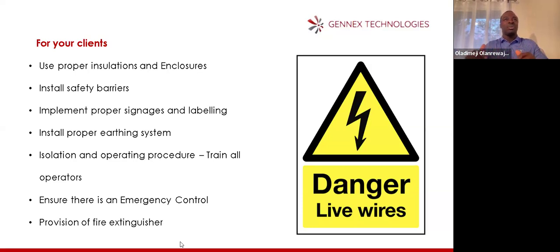I've gone to a site where all the cables used for the inverter connection were red, no color coding at all, the live red, the neutral red, the earth red. So before you can even start looking at it, you need to do a lot of work to isolate which one is the earth and which is the neutral. That's a very poor design.